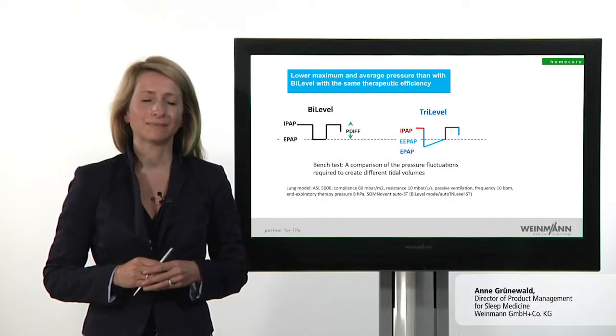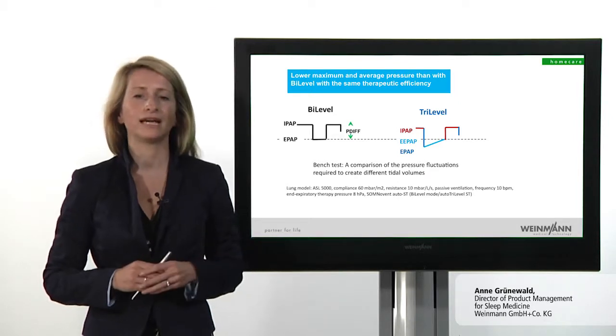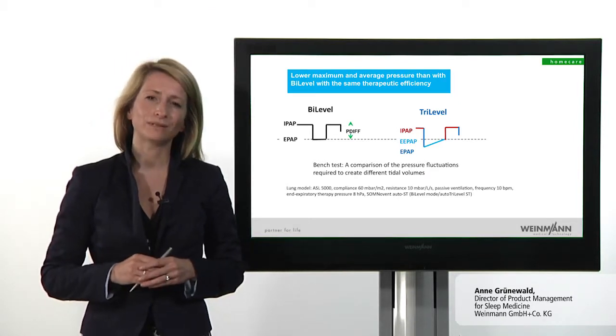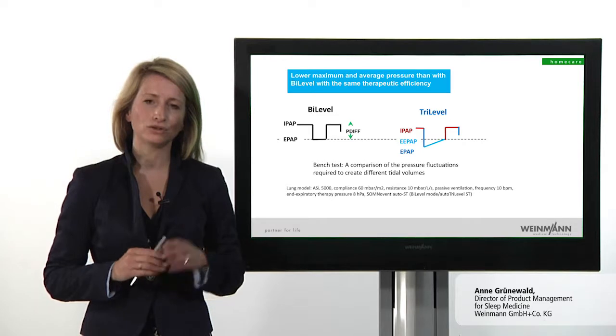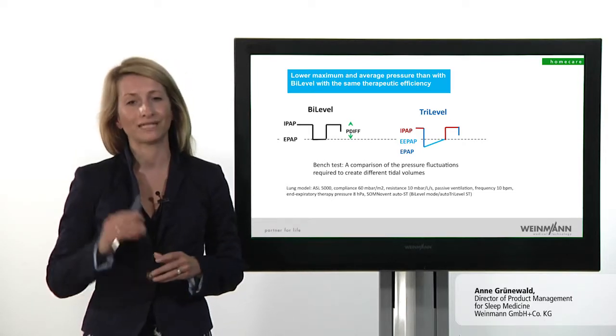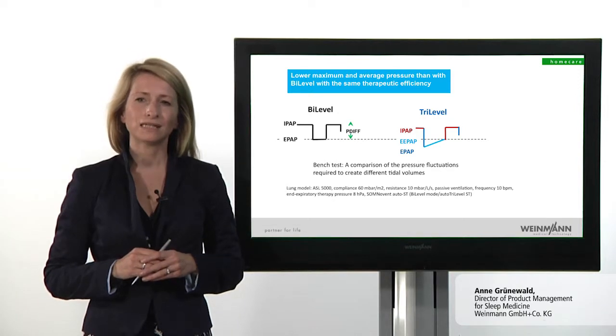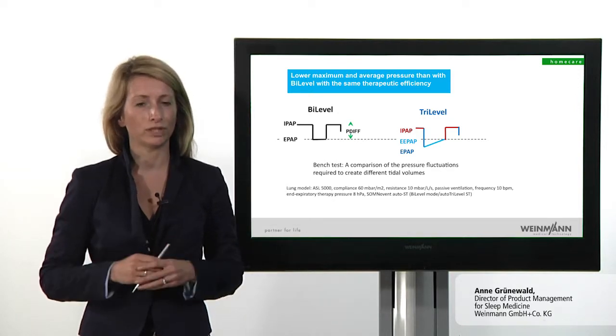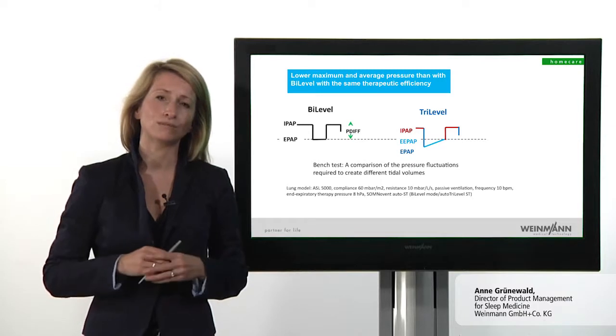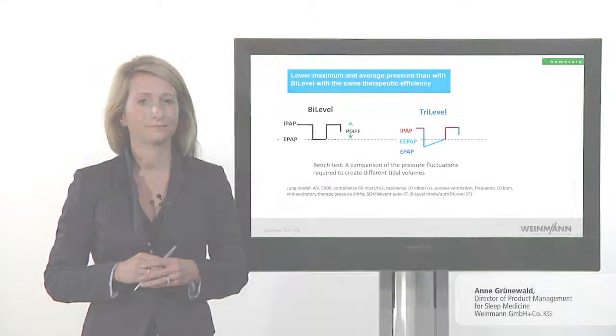What's more, a recent bench test has shown that by further decreasing pressure in comparison to classic bi-level, Tri-Level can achieve both average and maximum pressure levels which are lower by more than 2 hPa and still have the same therapeutic efficiency. In turn, this can result in fewer adverse side effects — for example leakages — and achieve more comfortable breathing and higher compliance.